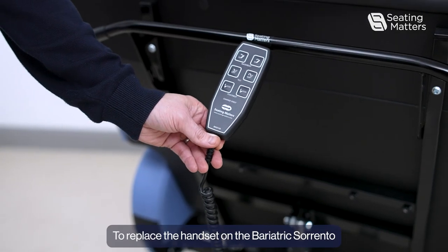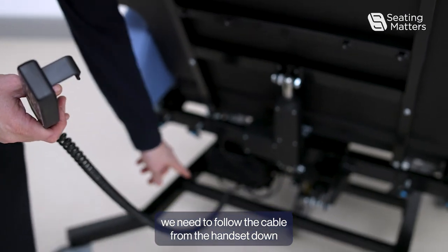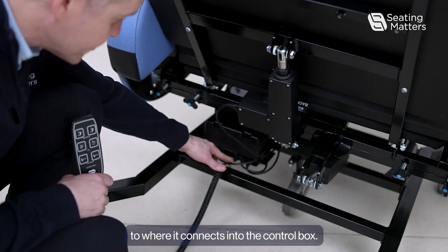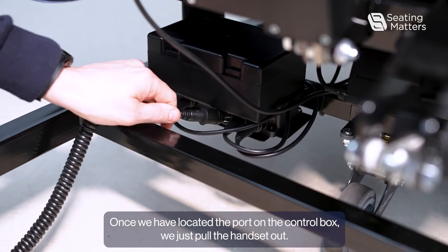To replace the handset on the Bariatric Sorrento, we need to follow the cable from the handset down to where it connects to the control box. Once we have located the port on the control box, we just pull the handset out.